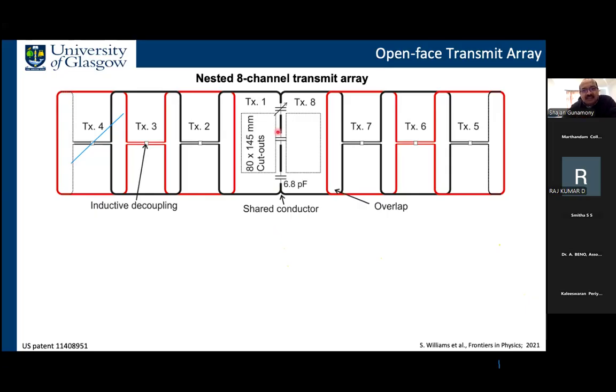The decoupling in the center is different because we wanted to have space for these large cutouts. If you have this overlap in the center between 1 and 8, then the size of this cutout will be smaller. It's also not as simple as putting a hole in the plastic, because the coil is an antenna. It also has an RF shield, so we are making a cutout in the RF shield. So we had to balance the magnetic field distribution of the coil.